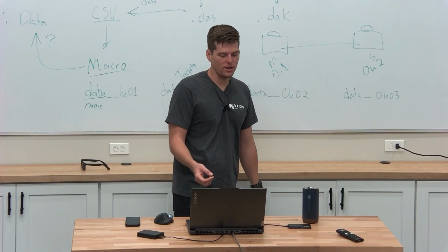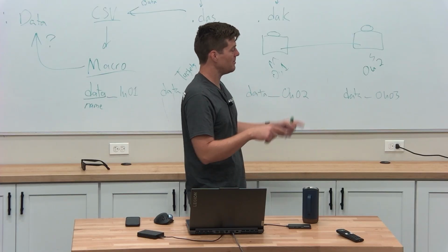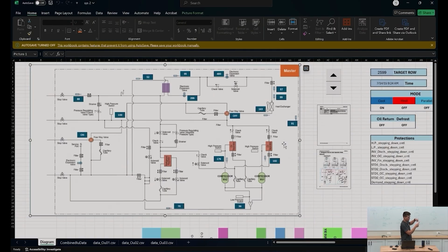I could go back and I could look at this, and you're going to find this in modules. You look in the outdoor module and you're like, man, that line's frozen, but that one's not. What the hell's going on? And you look at the data here, and I could say, okay, well, from this point, right, 97 degrees to 95 degrees here, like, what if this was 97 and this one was 20 degrees, right?